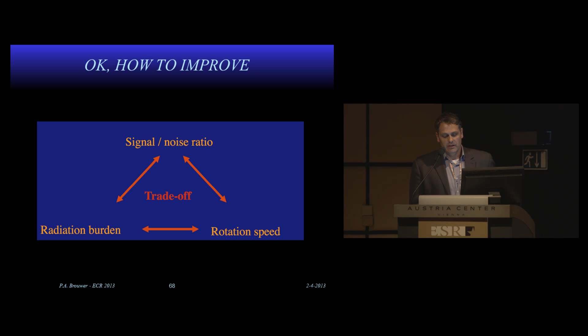So it's a trade-off between the signal-to-noise ratio, which we want really nice, and the radiation burden on one side, and the rotation speed of the machine at the other side. The rotation of the gantry of the machine is 1/3 of a second, so you actually get 3 frames per second imaging.